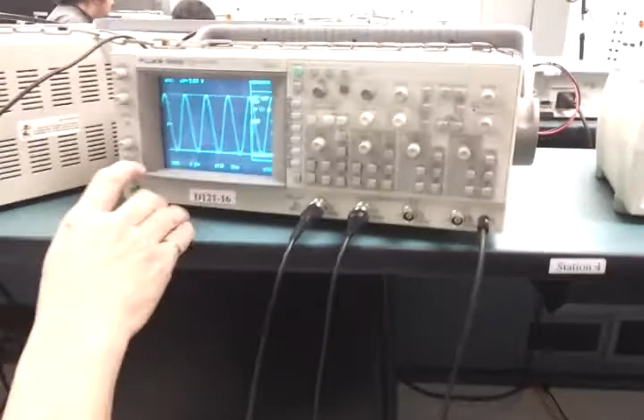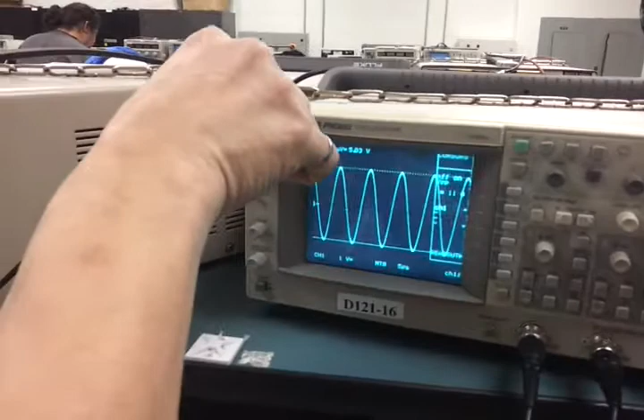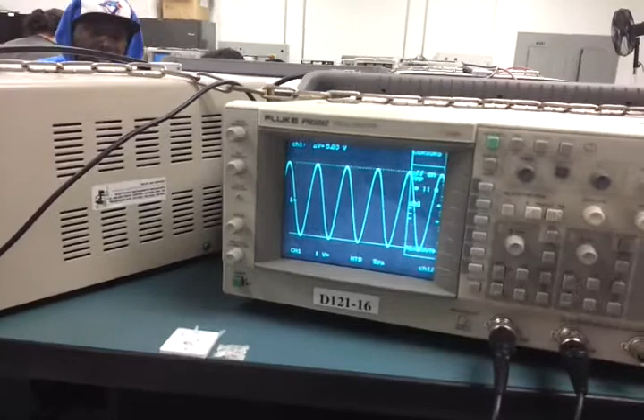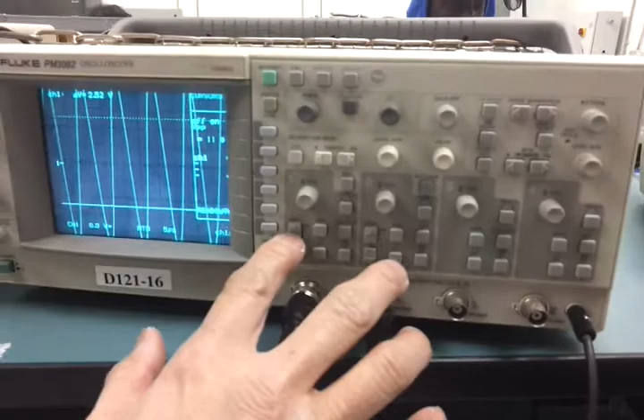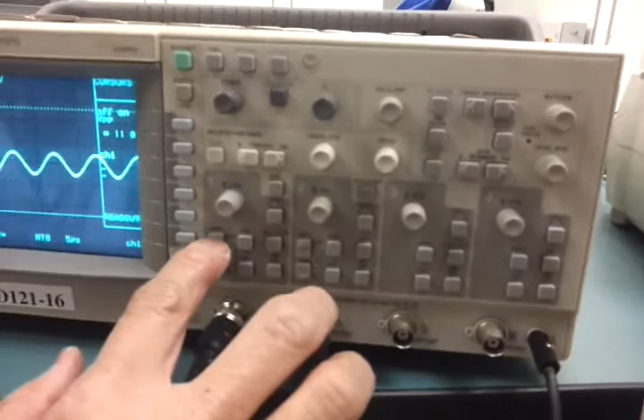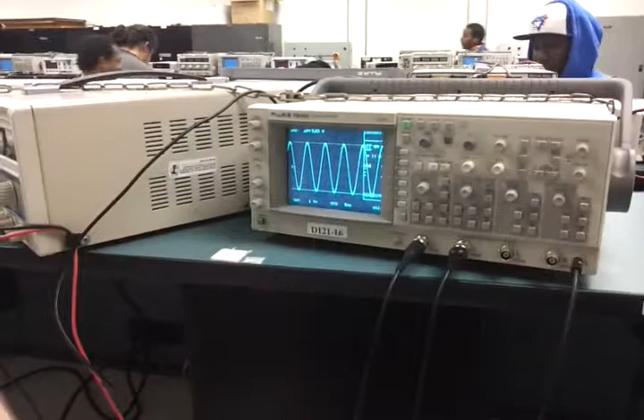Trace illumination and focus knobs. Trace illumination, trace intensity. If you don't see anything, then brighten it. If it's too bright, you're going to burn out the screen, so this is kind of okay. And voltage sensitivity adjustment, you can use these two buttons to turn the voltage sensitivity to higher voltage sensitivity or lower voltage sensitivity. So that's how you resize the voltage. But you're getting exactly the same voltage, just that the voltage looks smaller or bigger.